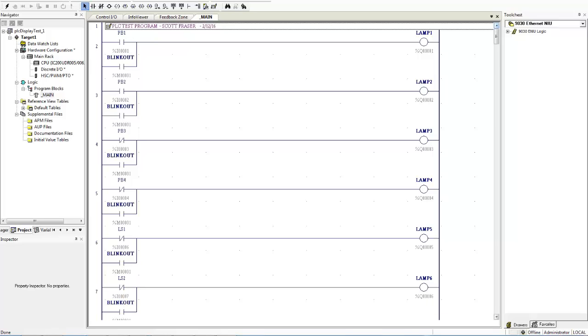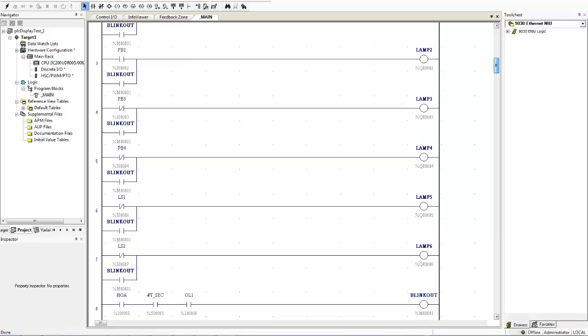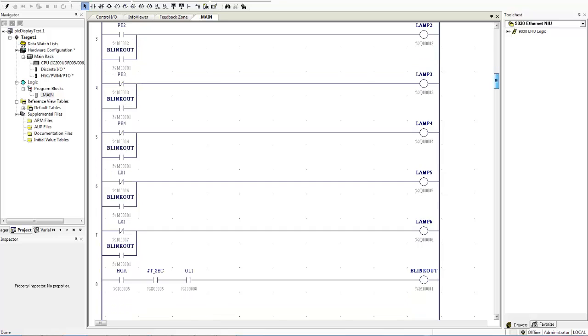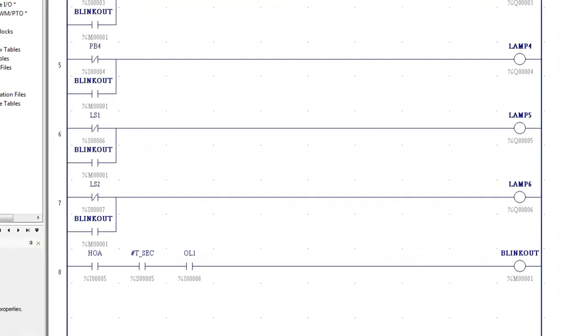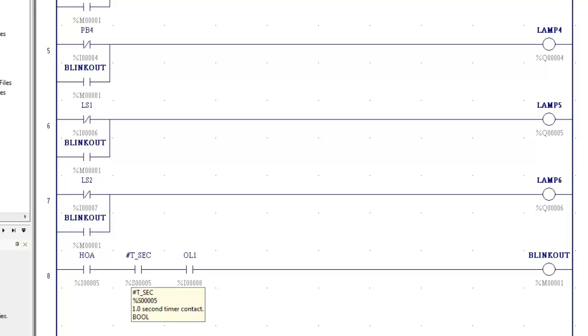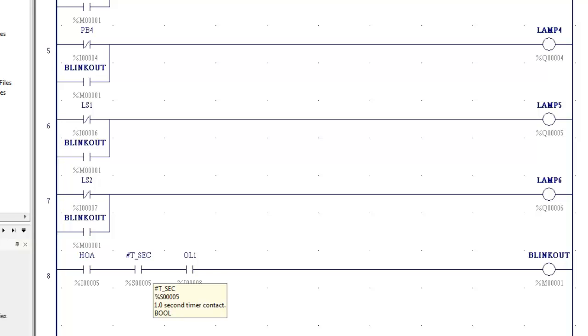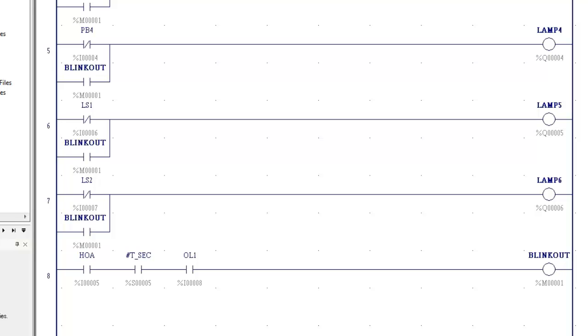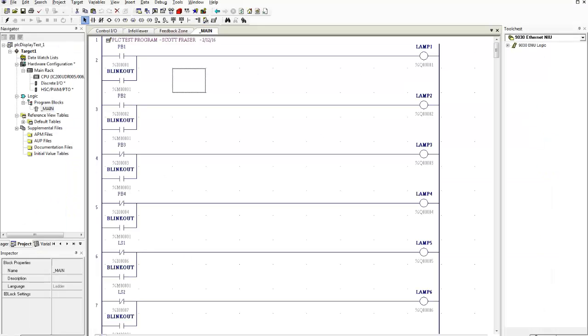Now that leaves us with two untested input switches. So we have down here. This is where that memory coil comes in. I have our HOA switch, a little timer contacts and the overload contact. So we need our HOA to be closed and overload one to be closed and these timer contacts close and that'll turn on this coil blink out. When that turns on all of these blink out contacts will close and all of your lights will start blinking at one second intervals. Okay. We have our program here.